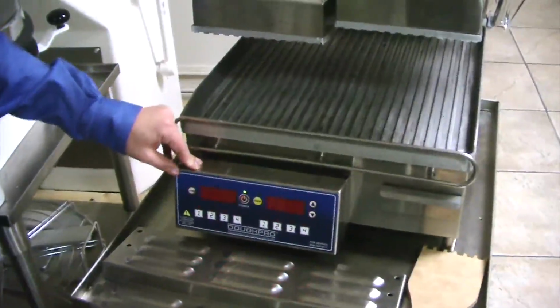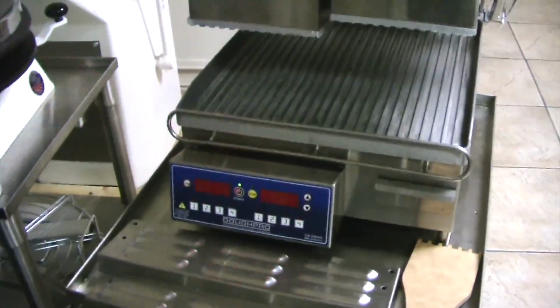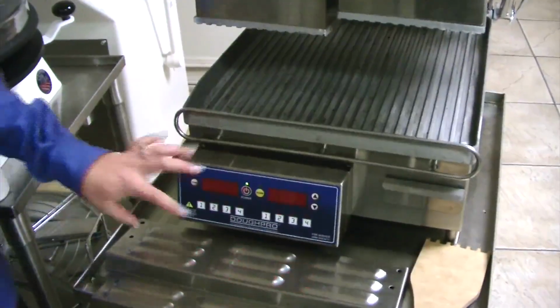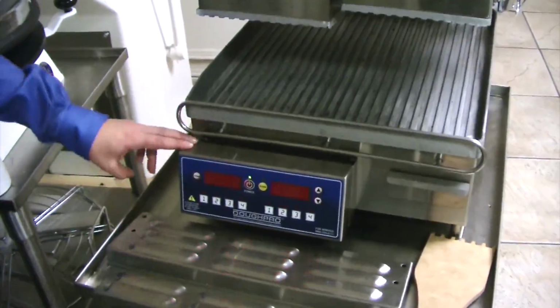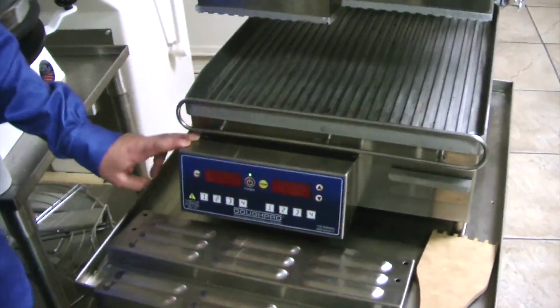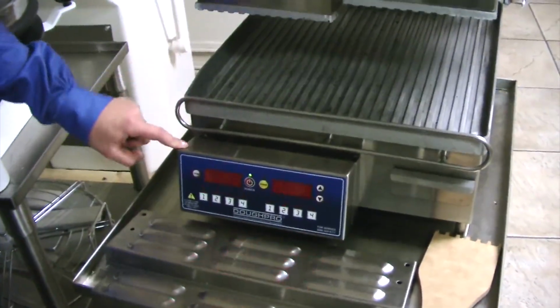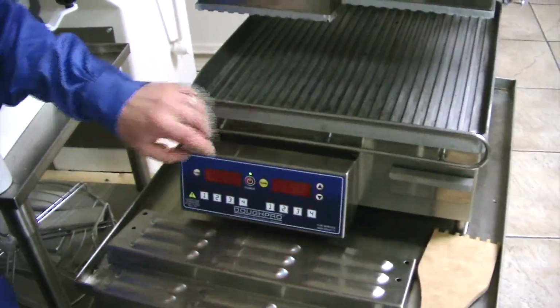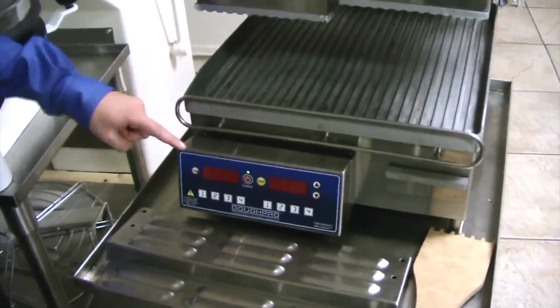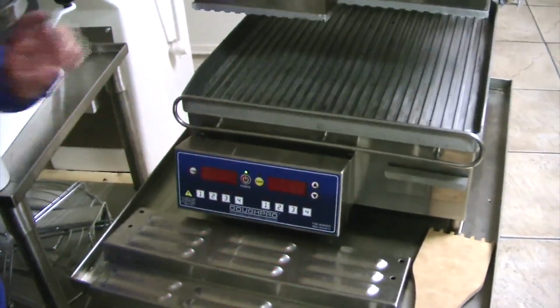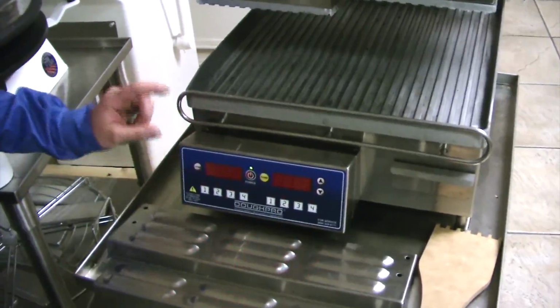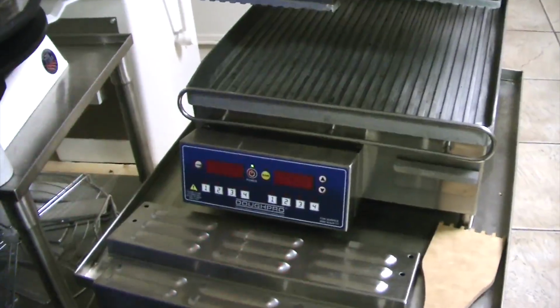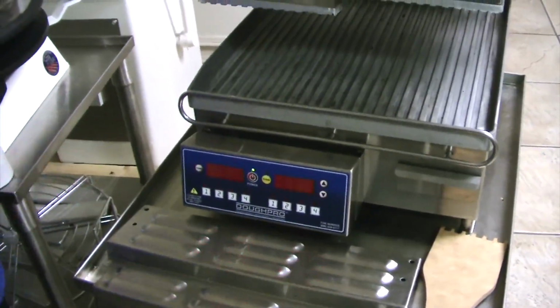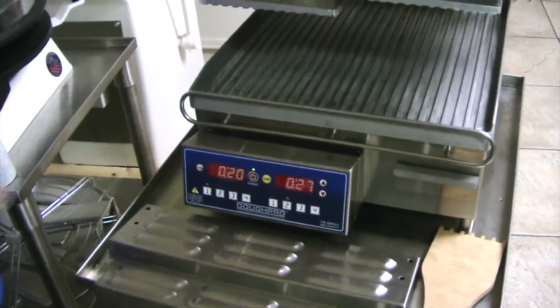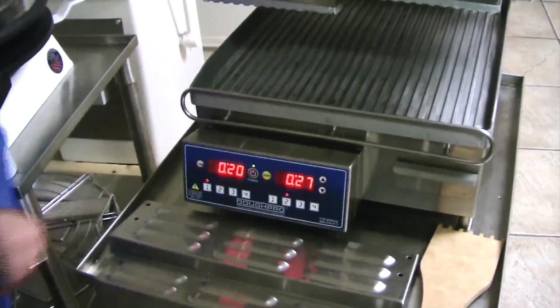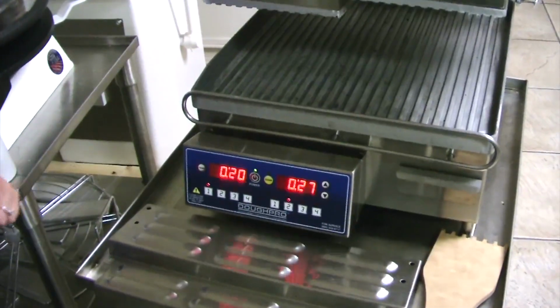Say the LED lights on the control are scrambled or giving you some weird code message that's not RELA, because RELA stands for relay, and PROB stands for probe. Now if it says anything other than those two, what you can try to do is leave your machine on, your controller on, and unplug it straight from the wall. You want to leave it unplugged for about 30 seconds to a minute. Plug it right back in and turn it on, and what that does is it resets the control.